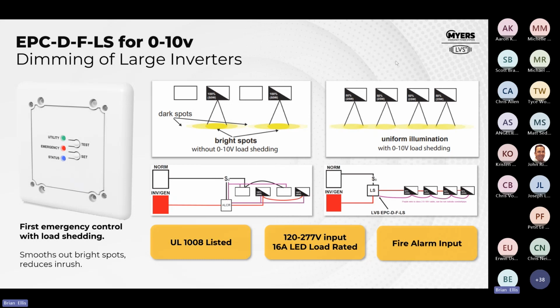So what we're suggesting is, if we're not using the micro inverter for that circumstance, you can use a central inverter or generator and then put in this load shed device. And it has two settings. You can set the dip switches for 5 volts or 2.5 volts. 5 volts would get you probably roughly the same result as over here as far as your inverter or generator size, right? Instead of every other fixture at full light output, you're at every fixture at 50%. But we really don't even need that if we're using every fixture. So we can set the dip switch for 2.5 volts. And now we've simplified the wiring, right?